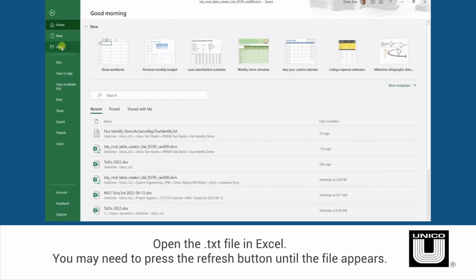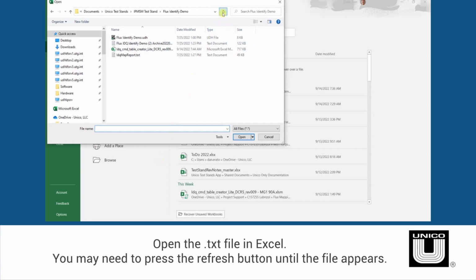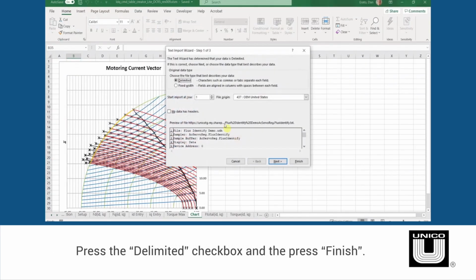Next, go to an Excel spreadsheet and open the recently saved text file. You may need to select the Refresh button until the file appears. When opening the text file, make sure to select the delimited checkbox and then select Finish. In the spreadsheet, you can see the following variables saved via the DCR5 data sampler: D-axis current request, Q-axis current request, D-axis current feedback, Q-axis current feedback, D-axis flux feedback, Q-axis flux feedback, torque calculation, Unico's torque estimation, torque transducer feedback, velocity feedback, and bus voltage feedback.